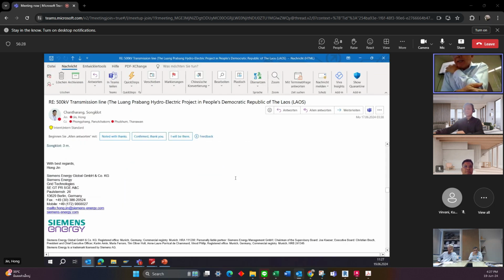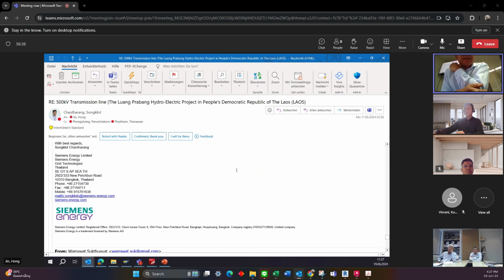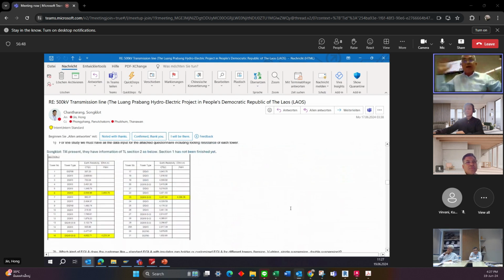For example, we don't know whether the span length is a factor or not. The nominal span length for this project is 440 up to 450 meters, but the actual length may vary from this. Is it possible that one surge arrester can cover more than 2 or 3 towers, back and ahead span, so that we can share the effective performance of the arrester to cover more than one tower, not just depending on the footing resistance? No, unfortunately not.